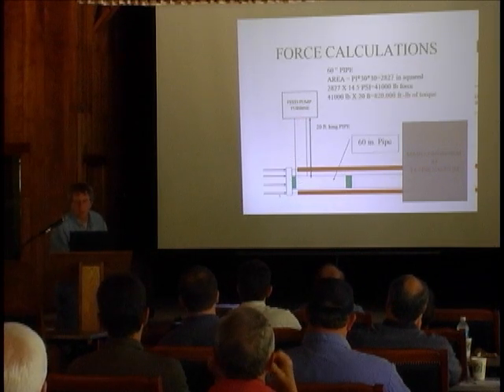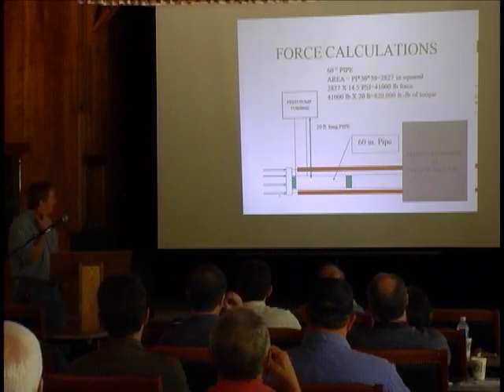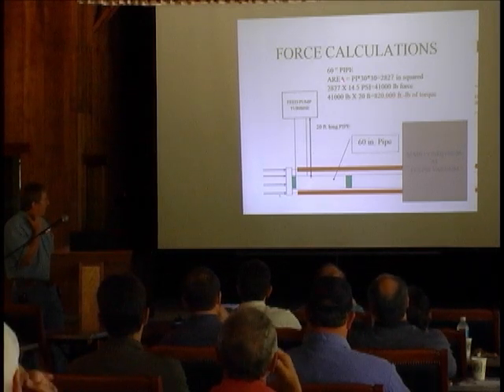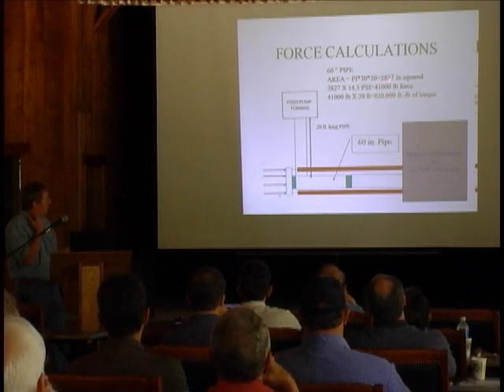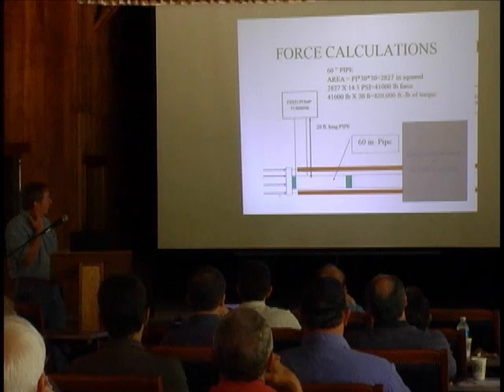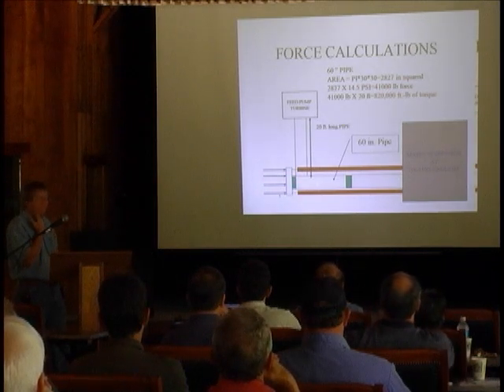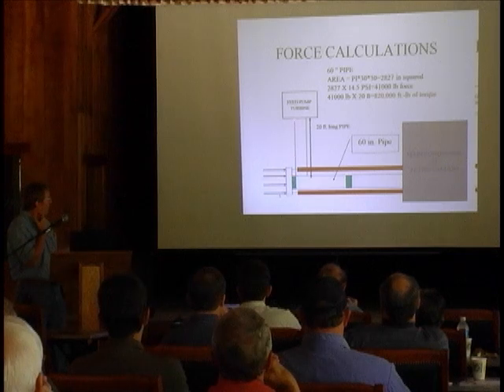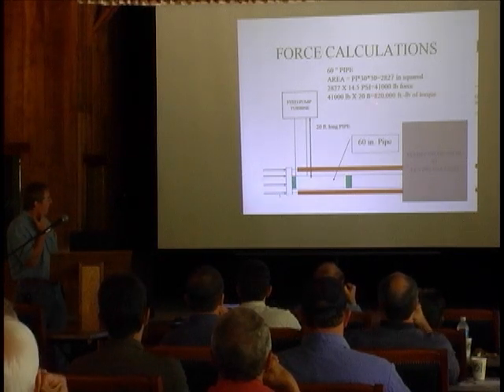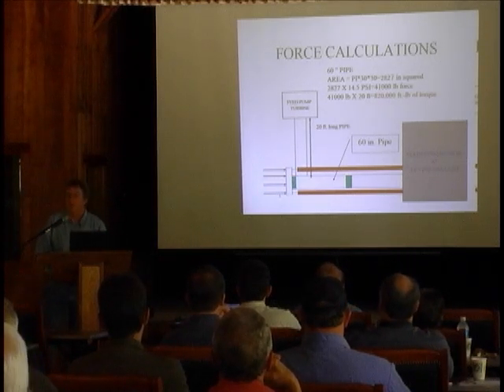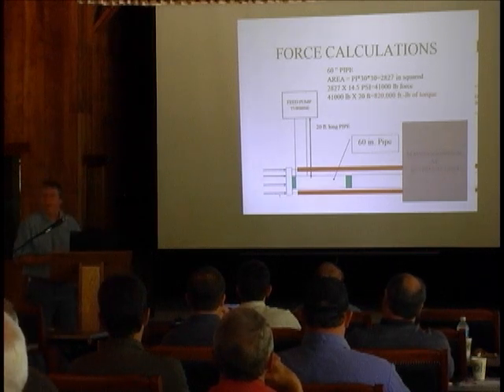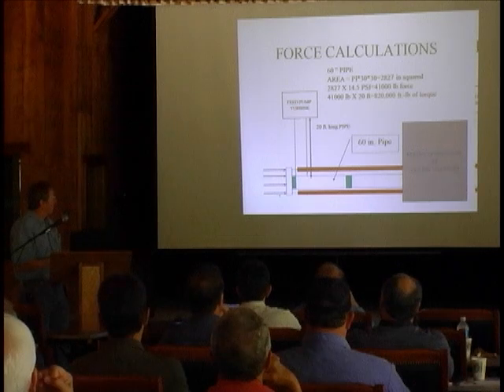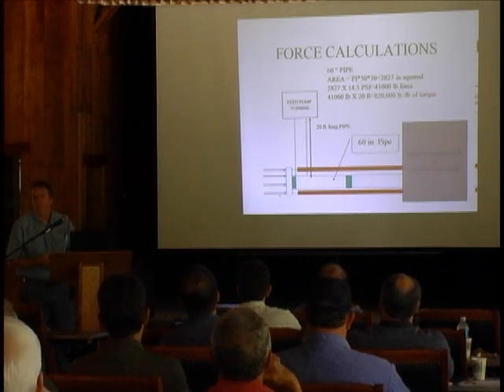And I did some calculating here. It has a 60-inch diameter pipe. The area, pi r squared, is 2,827 square inches. You take that times 14.5 psi, is 41,000 pounds of force pushing this way. The length right here of this pipe is 20 feet. That's 820,000 pound-feet of torque. That's basically all being applied right here to the base of your turbine whenever you draw vacuum on this.